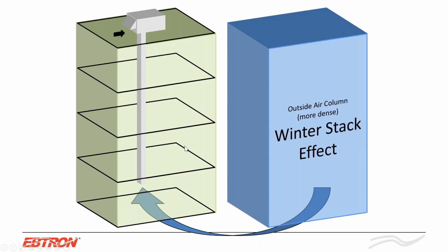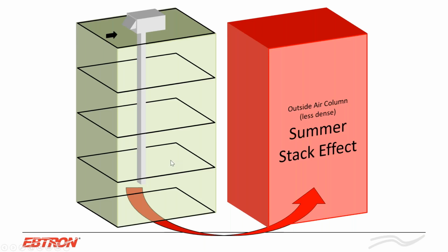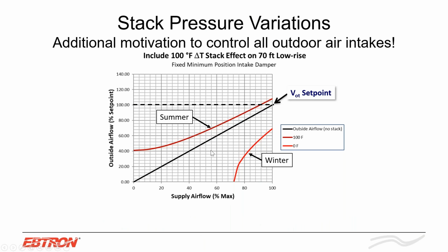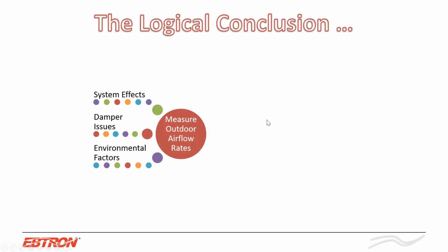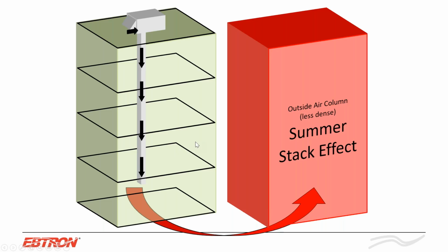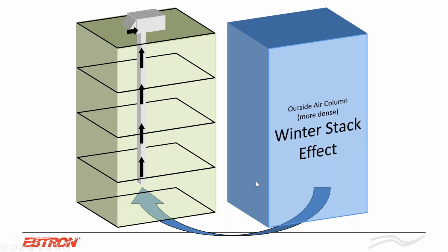So like for Boston, winter stack effect could be an issue. So this is just looking at a simulation again, 70-foot low rise with 100-degree differential. Again, in the summer, you're overventilating, and in the winter, you're severely underventilating the space if you're not controlling the outside air intake, right? So what do you want to do? You really want to measure and control your flow rates. And what engineers are doing for stack effect, because there's never a way to completely eliminate it, is zone and floor level control. And then they are compartmentalizing with basically a damper flow meter combination, again, on each zone or each floor to help mitigate some of those stack effect issues that you will see.